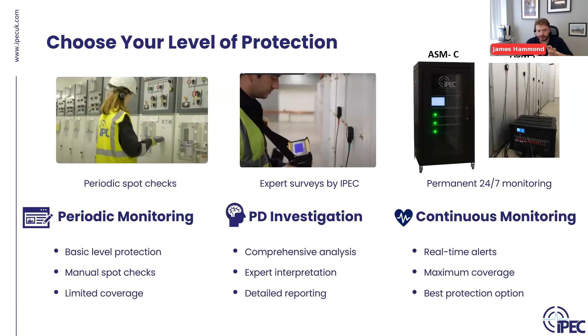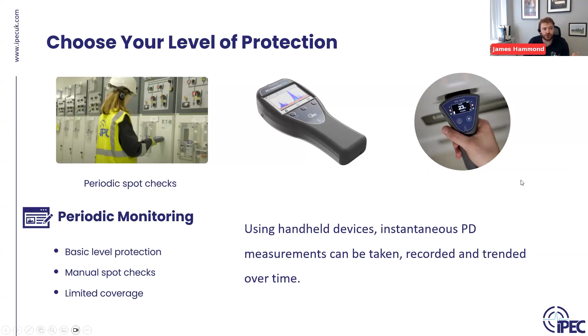This level of protection can be chosen - it doesn't always have to be the full end or the bottom end, it can be somewhere in between, a hybrid. Something like periodic monitoring, as I mentioned, spot checks - using the condition of the asset to make engineering decisions. Using a handheld device to get that instantaneous PD level is one way you can protect your assets.